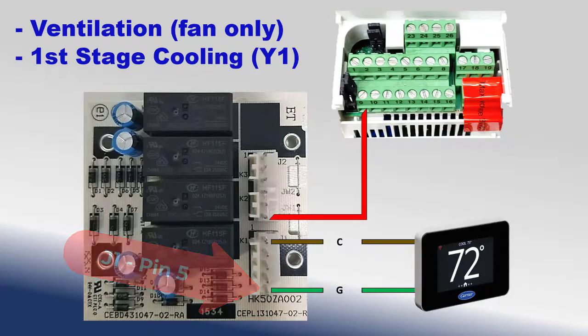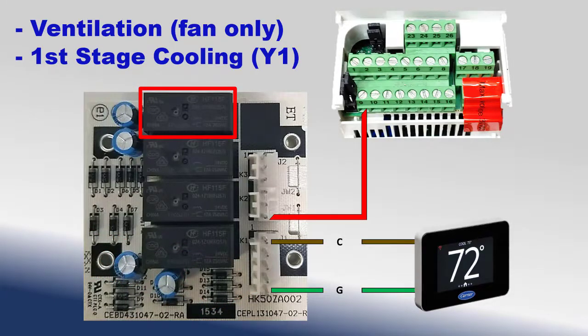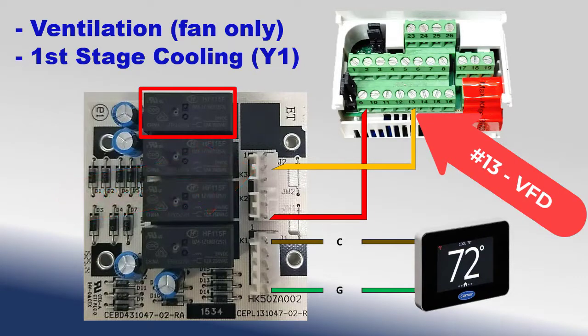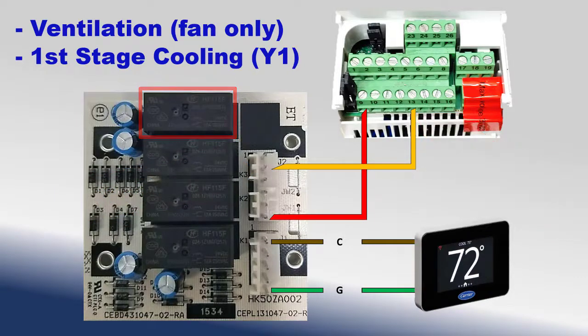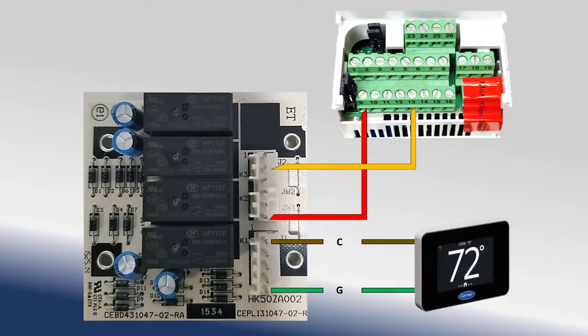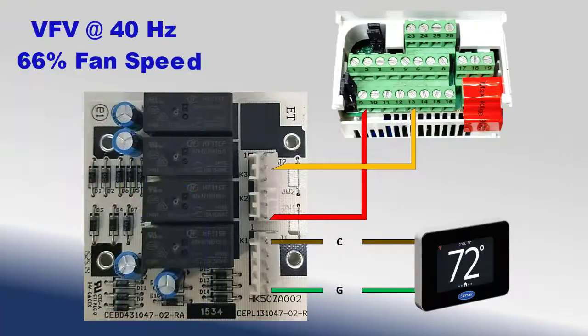This 24-volt AC signal closes relay K4. When the K4 relay is closed, the 24-volt DC signal from the J2 terminal pin 6 is closed to J2, pin 2, which is returned to the VFD at terminal 13. This input initiates a command for the VFD to come to 40 Hz, running the motor at 66% of fan speed.